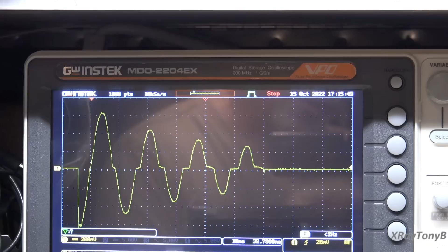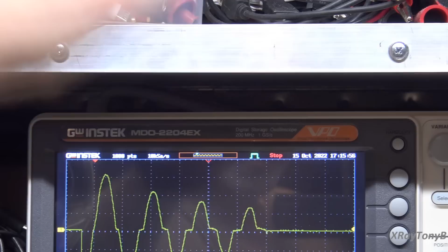The first thing I want to tell you is the way I am looking at this. This is your mains voltage dropping across that inrush current limiter, and it is connected to mains, so you do not want your oscilloscope directly connected to mains. In order to do that, we're using this little device called a differential probe. This is an isolated probe, and it isolates the mains voltage from your oscilloscope. So the output of this is isolated from the input. Very important: never connect your oscilloscope directly to mains. Bad idea. There's lots of videos on that, and I even did one on it.